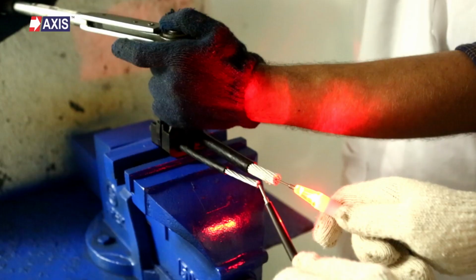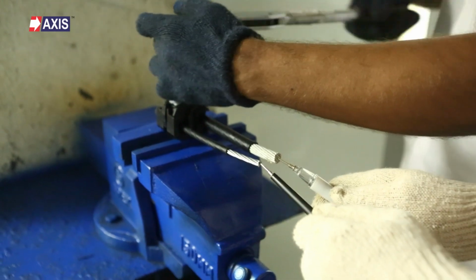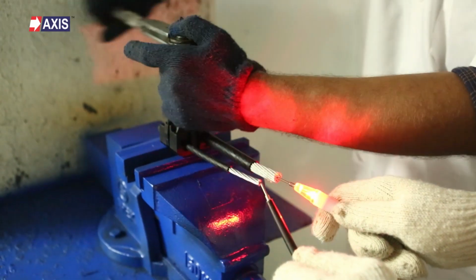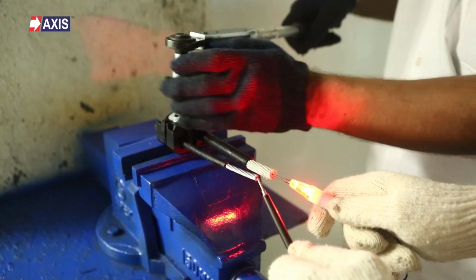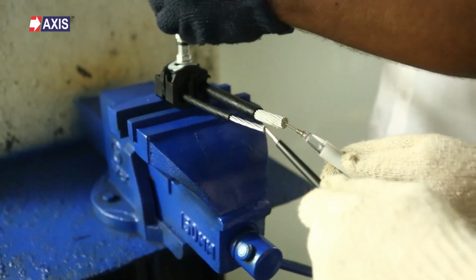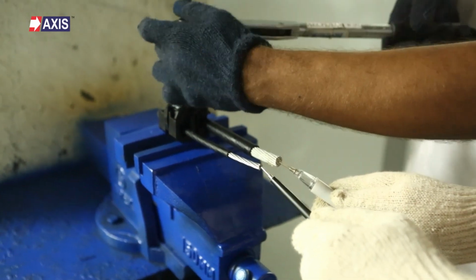Firstly, the continuity test. Continuity is the presence of a complete path for the current flow. This test confirms the continuity of the current across an IPC. To perform this test, you can use either a continuity tester or a meter equipped with a continuity beeper. In the case of the tester, if the light glows, it implies that the continuity is proper. As you can see here, in the case of the Axis IPC, the light glowed. This confirms that our IPC is correctly connected to both ends of the cable and has properly established connections.